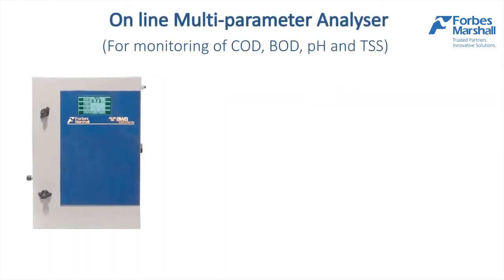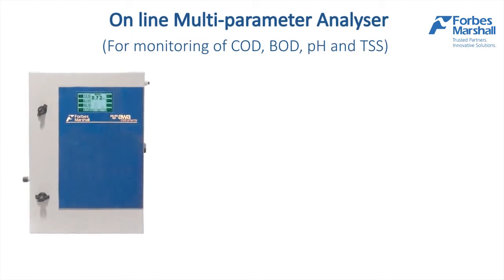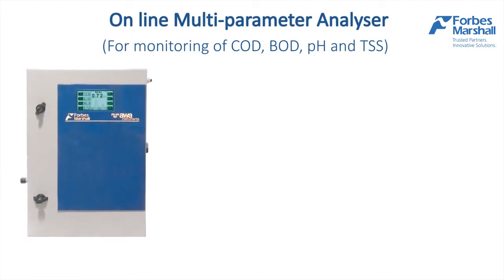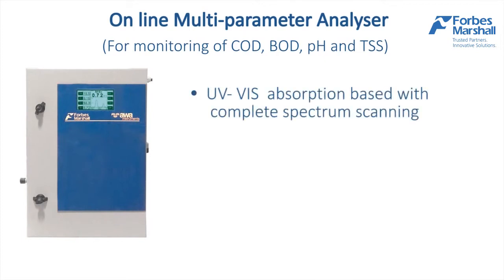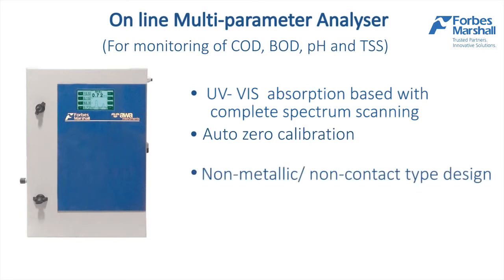Online Multiparameter Analyzer: This is for monitoring COD, BOD, pH and TSS. The measurement principle is UV-Vis absorption based with complete spectrum scan. It provides auto-zero calibration. It is a non-metallic, non-contact type design. The measuring cycle is programmable.